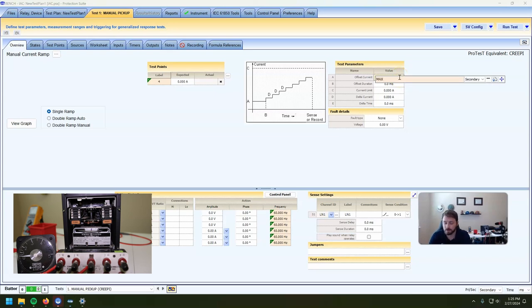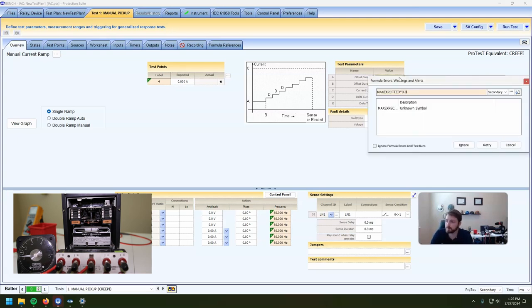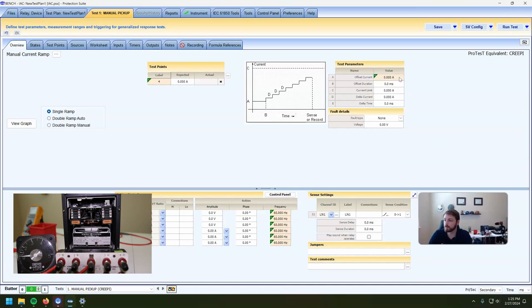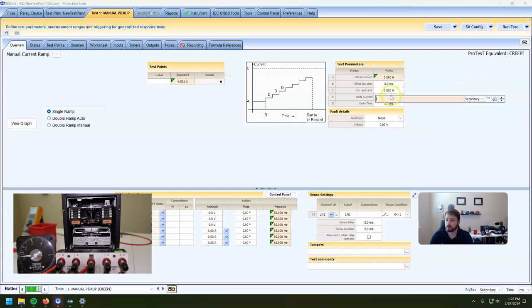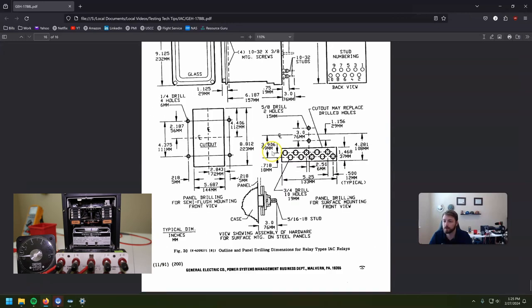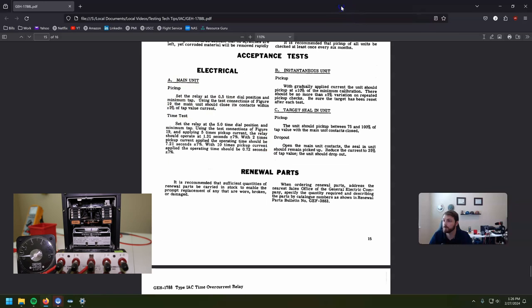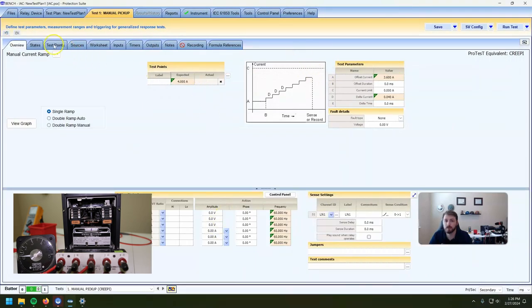Our offset current — you could really start from zero, but I like to shave this down a little bit. We'll do one percent steps, that should be fine. Out of our manual, we had plus minus five percent of the tap for accuracy. So under test points, tolerance: plus minus five percent. Cool beans.